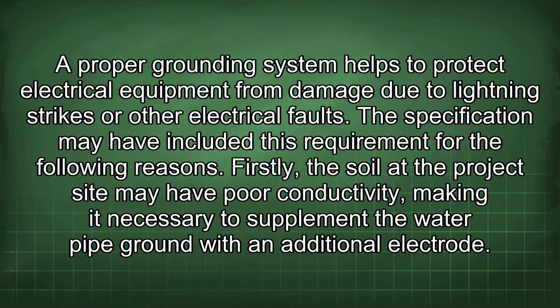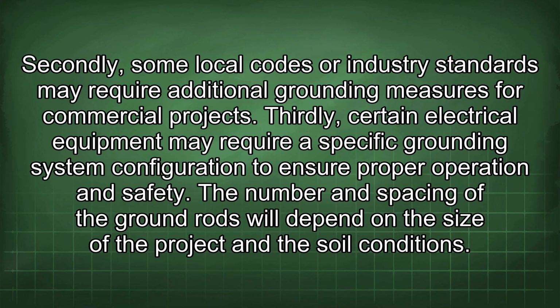The specification may have included this requirement for the following reasons. Firstly, the soil at the project site may have poor conductivity, making it necessary to supplement the water pipe ground with an additional electrode. Secondly, some local codes or industry standards may require additional grounding measures for commercial projects. Thirdly, certain electrical equipment may require specific grounding system configuration to ensure proper operation and safety.